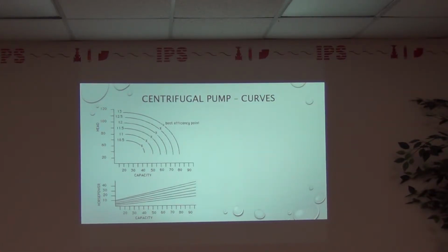So you've got multiple different impeller sizes, which is typical to any pump. Notice on the bottom here, we've got 10 and a half. You see that gap, that low flow, 20 gallons per minute, or capacity 20, 30, 40. That's what I was talking about with the peripheral pump. Just on principle, that's the toughest area for a centrifugal pump to hit. If you're riding so far to the left or so far to the right, you're moving too far away from your best efficiency point, so the pump becomes inefficient and potentially would wear a lot faster than a pump that was selected right for the application, which you see all the time.